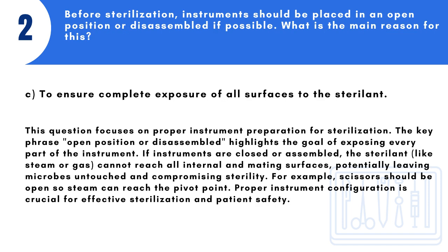Answer: C. To ensure complete exposure of all surfaces to the sterilant. This question focuses on proper instrument preparation for sterilization. The key phrase open position or disassembled highlights the goal of exposing every part of the instrument. If instruments are closed or assembled, the sterilant, like steam or gas, cannot reach all internal and mating surfaces, potentially leaving microbes untouched and compromising sterility.